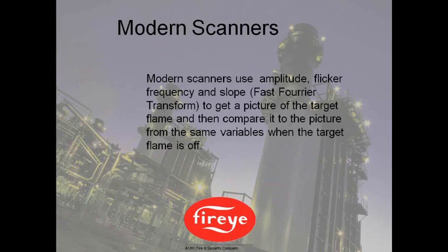So the typical tests that we use are flicker frequency, amplitude, and the slope to get a picture of the target flame. We then compare that picture to the other variables when the flame is off.